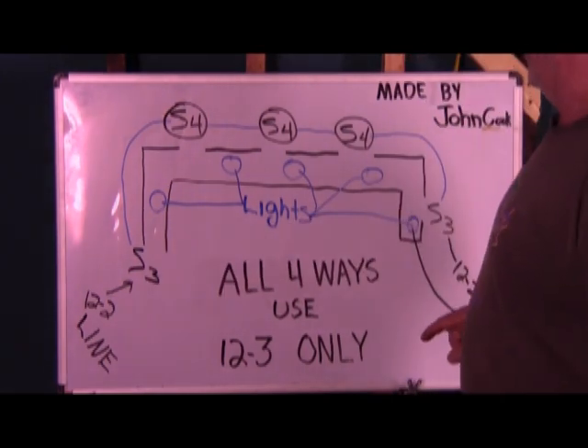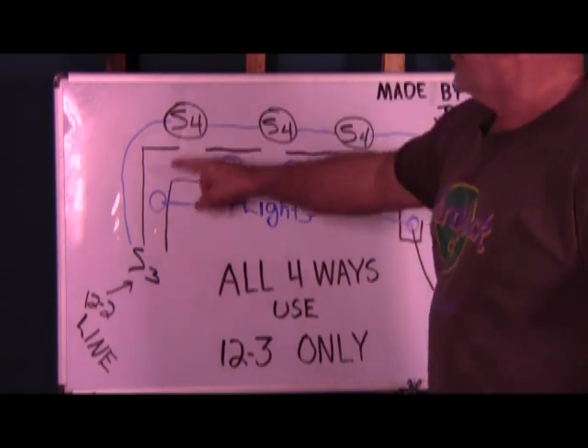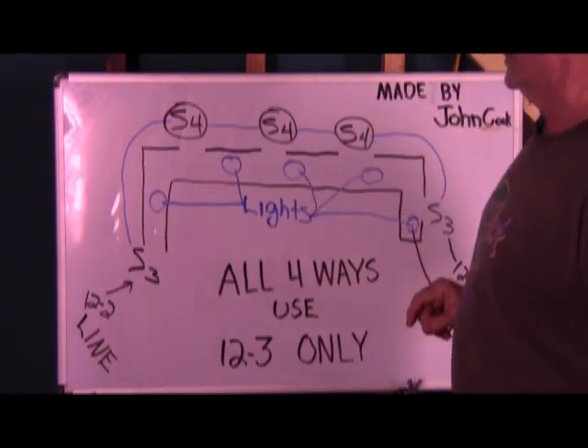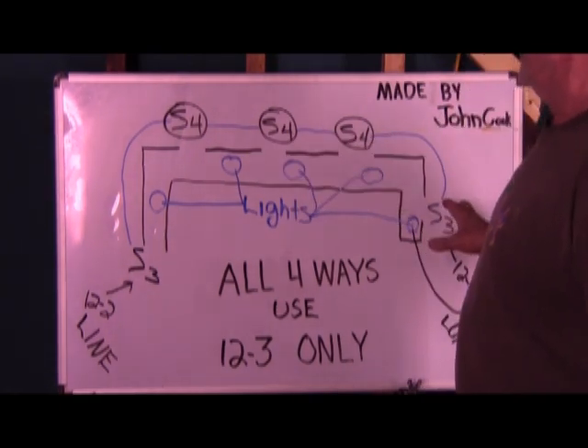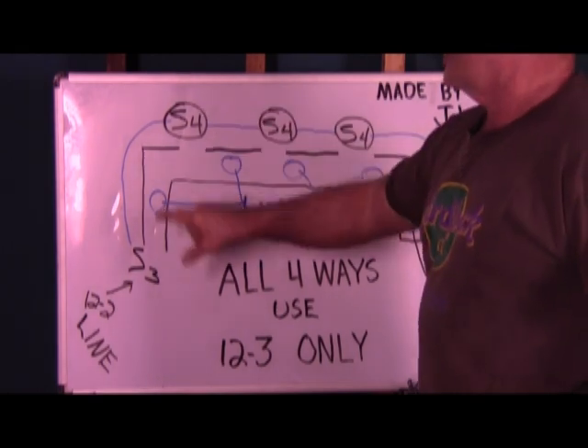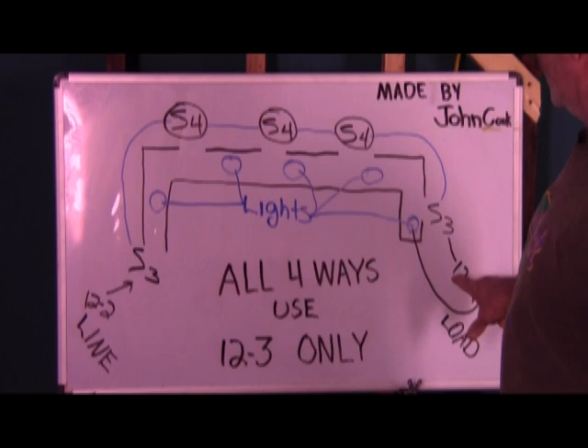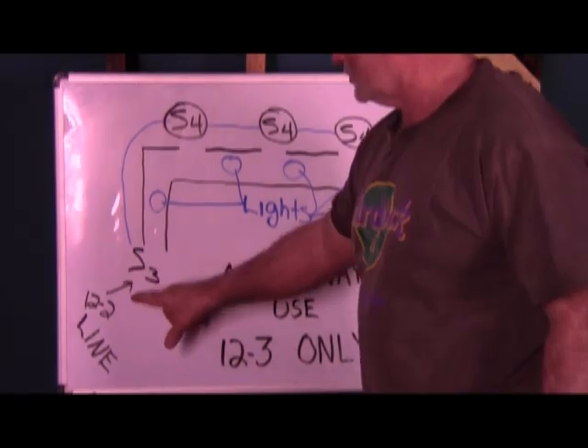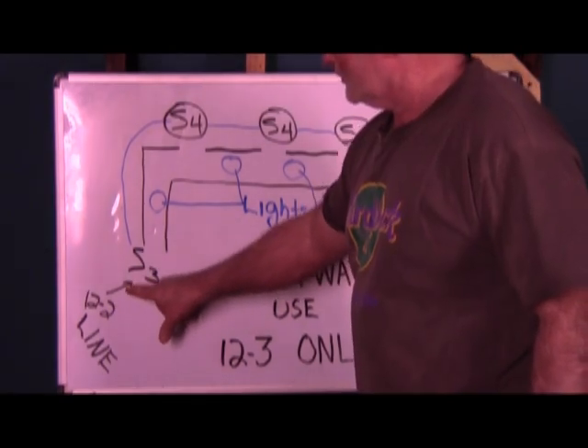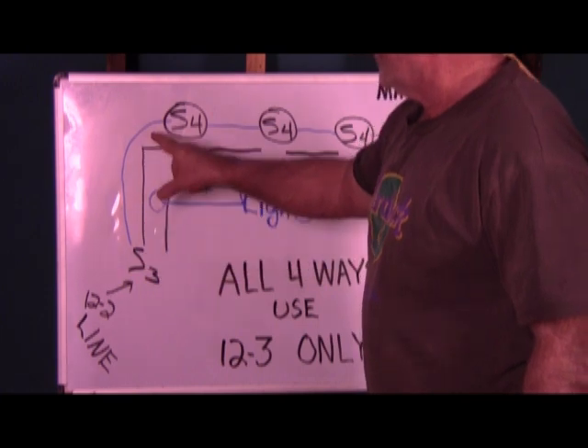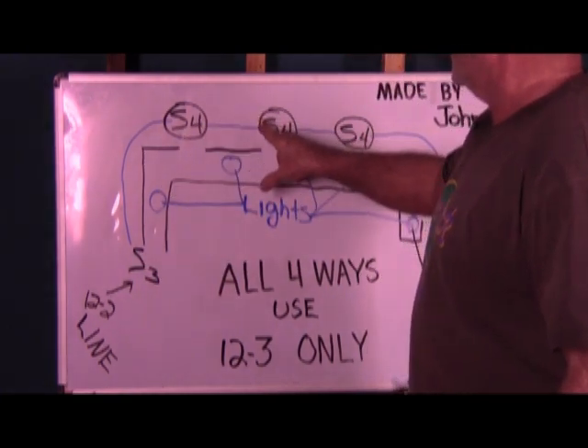Now in between those three-way switches, you can have as many four-way switches as you like. The lights all go to the load three-way. First switch three goes to a twelve-two. Everything from there is twelve-three.